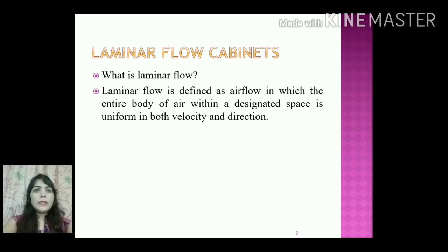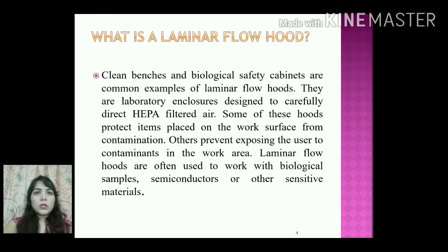Laminar flow is defined as airflow in which the entire body of air within a designated space is uniform in both velocity and direction. So with the help of laminar airflow, we can have unidirectional airflow with constant velocity. So what is a laminar flow hood? Clean benches and biological safety cabinets are common examples of laminar flow hoods.